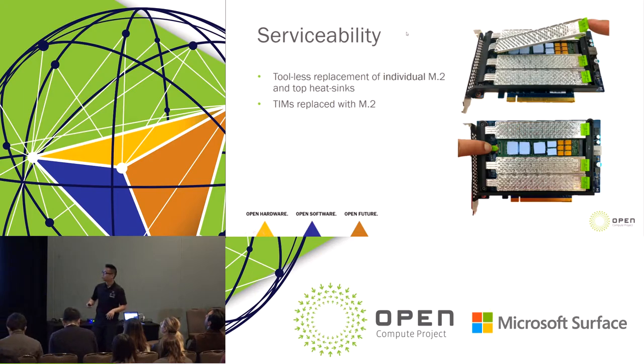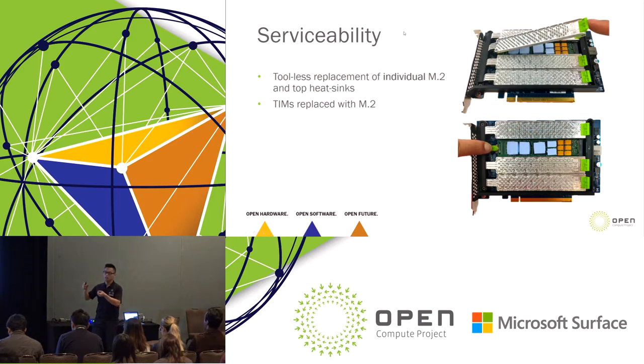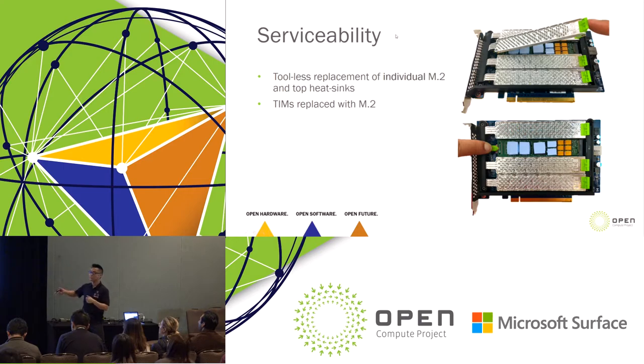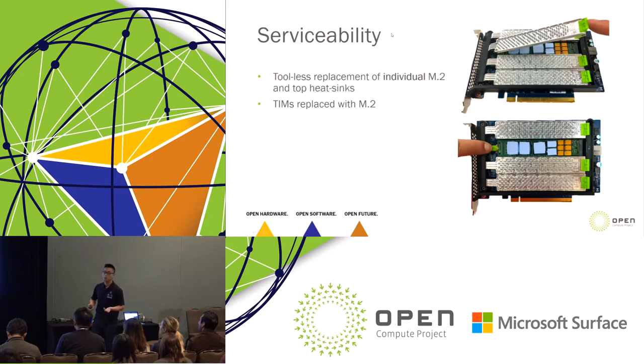Operationally, the complexity is in adding thermal interface materials to your M.2s and making sure that when you're replacing a new one it's not pre-compressed, but in general it enables a lot of flexibility. Walking through the main touchpoints: just lift the heat sink up, then actuate the latch on the bottom right-hand side and take out the M.2. Everything's tool-less and super simple.